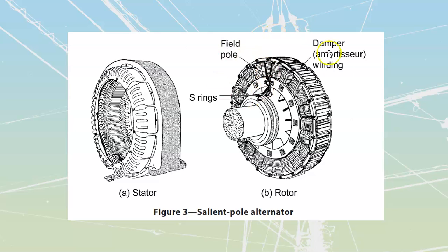Because it's much larger, it means we're going to have much more centrifugal force. So we have to use a prime mover that runs slower, at low RPMs for these ones. If we go too fast, we'll have way too much centrifugal force, which will actually start to pull these windings off of their individual components.